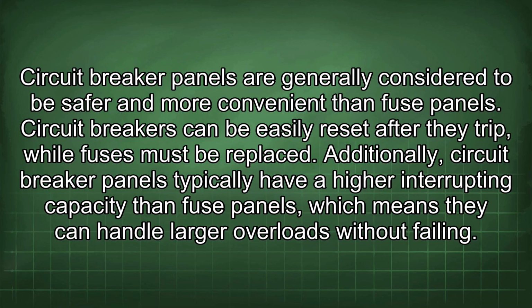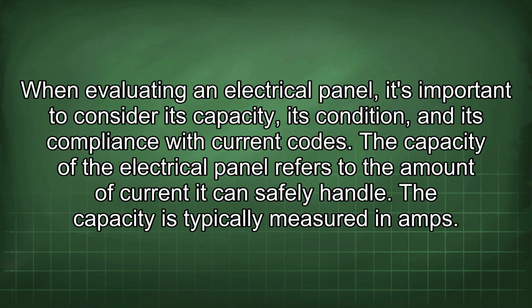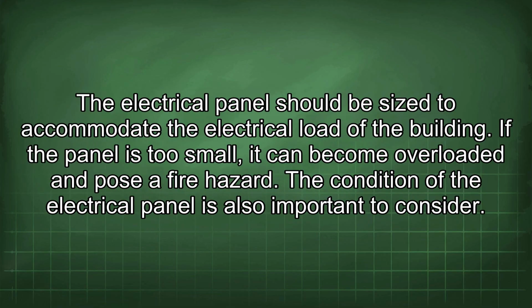Additionally, circuit breaker panels typically have a higher interrupting capacity than fuse panels, which means they can handle larger overloads without failing. When evaluating an electrical panel, it's important to consider its capacity, its condition, and its compliance with current codes. The capacity of the electrical panel refers to the amount of current it can safely handle. The capacity is typically measured in amps. The electrical panel should be sized to accommodate the electrical load of the building. If the panel is too small, it can become overloaded and pose a fire hazard.